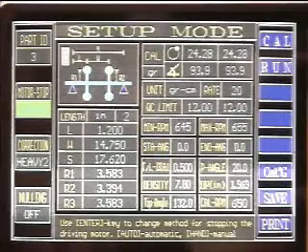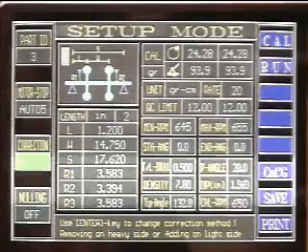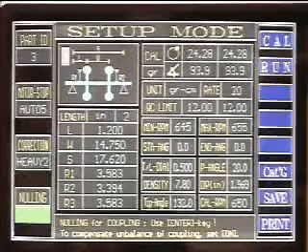Next is the motor stop option that determines how many samples per audit are taken. Currently it is set to auto 5 for 5 readings. Method of correction. Set this to light to add mass to balance the part, or heavy 1 for axial, or heavy 2 for radial correction to remove mass. Nulling, which is tooling compensation, can be turned on or off.